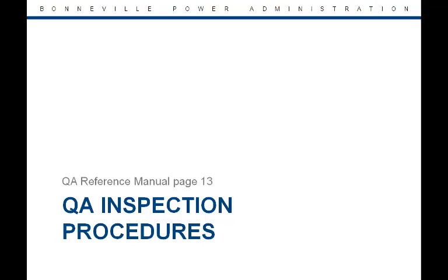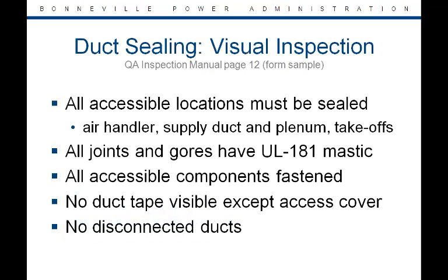In the Program Requirements document, BPA outlines the protocol for passing or failing an installation. This section discusses that procedure and can also be found in the QA reference manual. Duct sealing jobs are both visually inspected and tested during quality assurance. The PTCS specification requires that all areas must be sealed. Pay special attention to high-pressure areas such as the air handler, supply duct, and plenum, and takeoffs.